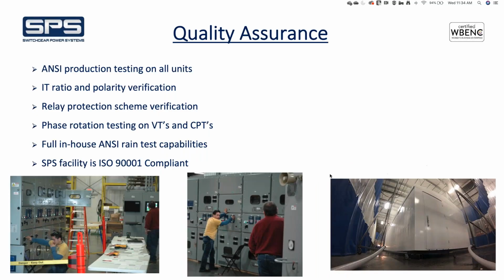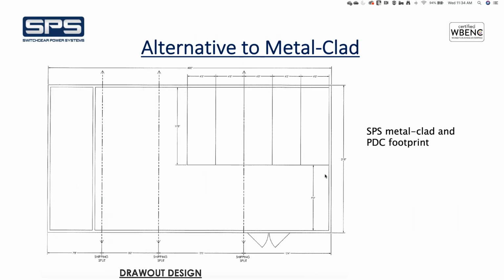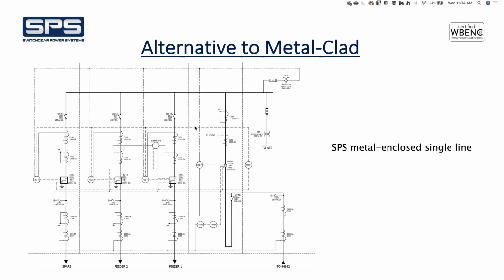Yeah, so let me go back to that. We bid them the project utilizing metal clad switchgear, and we offered them a voluntary alternate to go to this metal enclosed circuit breaker design. The deduct to go to the metal enclosed design was 12%. I don't remember exactly offhand, but it was from 1.1 something million down to less than $1 million for the total cost of the switchgear in e-house. Oh, you mean for this one with metal enclosed with one incoming, 3 feeders? Yes. Oh, okay. Yeah, so for that particular project, it was about 12%.